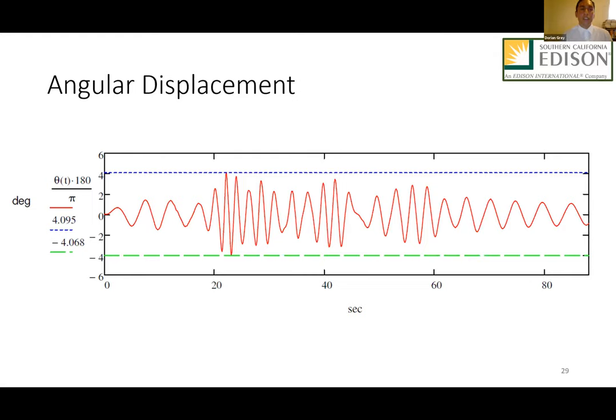Further analysis is still needed to be completed with respect to any impact forces that would result at the bus connections in the event that all the available slack in the conductors was used, since these connections are only rated for up to 2,000 pounds under dynamic loading. However, we never made it to that stage to analyze the forces at the foundational posts and the bus connectors. So that'll be the end of the analysis for our damper system.